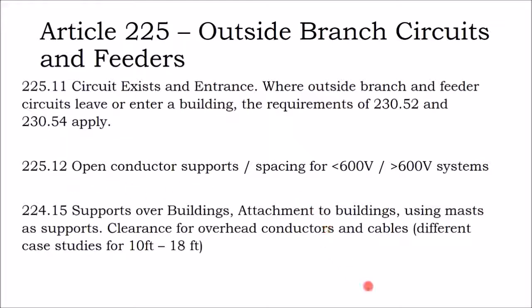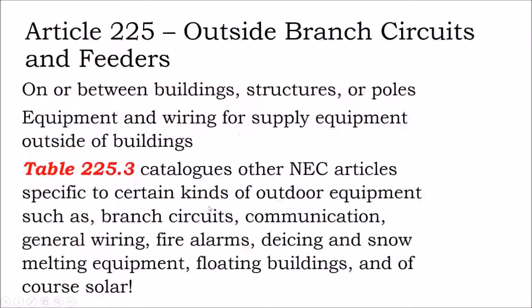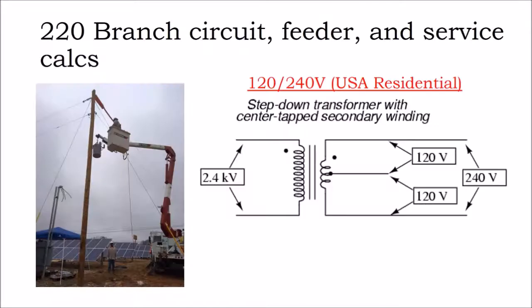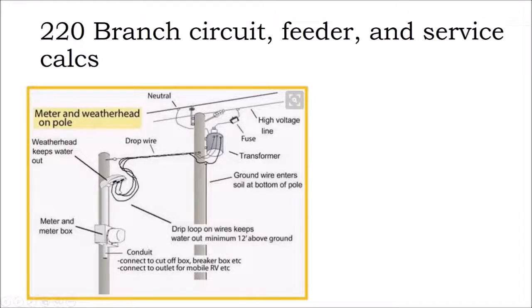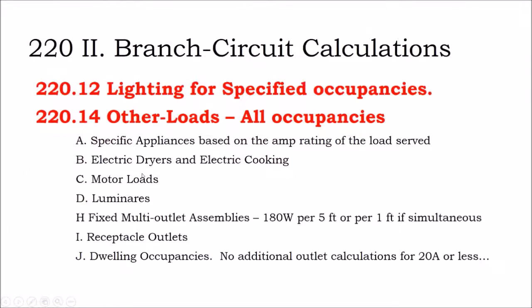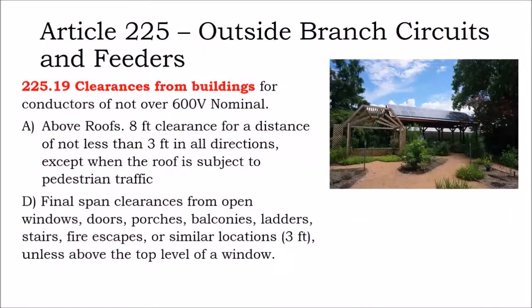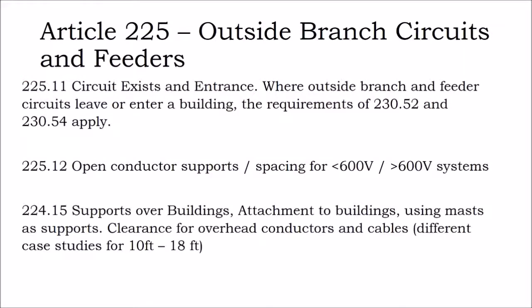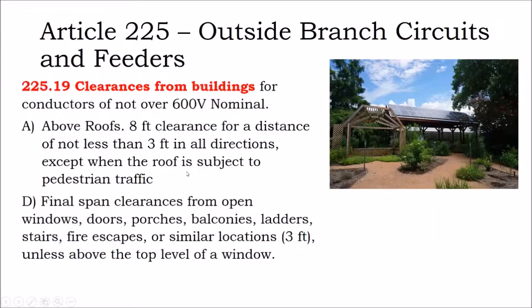Supports over buildings, attachments to buildings, using masts as support, clearance for overhead conductors and cables, and there are different scenarios going from 10 feet up to 18 feet of clearance requirements. This is where, going back a few slides to the crow's nest or the weatherhead, how tall does this weatherhead need to be for these power lines from the utility to just drop down and be taped up? These are overhead wires, so how tall does this need to be? Well, it's hidden right in the very beginnings of code, where we're still talking about feeder circuits supplying power to a service panel. Often it'll be an 18-foot clearance.